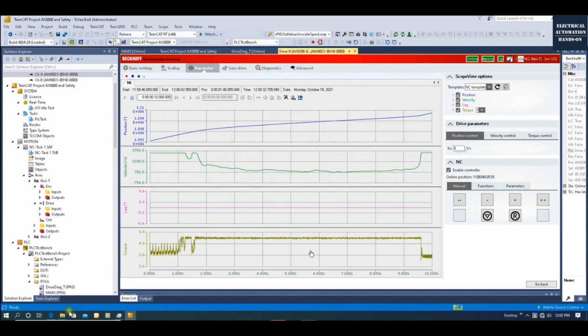Alright, this is the MC torque control. When we set a set point for the MC torque control command, the highest torque from the motor will be held under the 5. And meantime, the velocity will adapt. This is the typical case, especially when we are using rewind control.